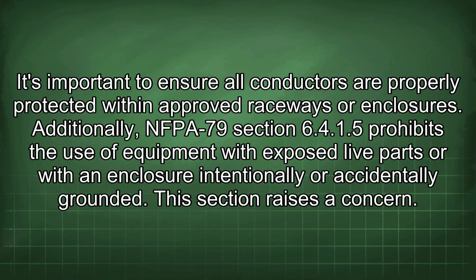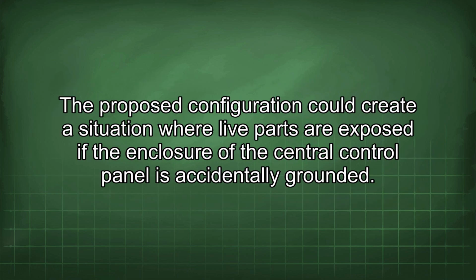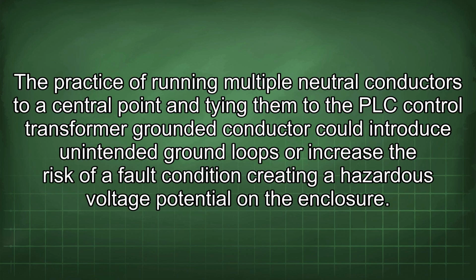Additionally, NFPA 79 Section 6.4.1.5 prohibits the use of equipment with exposed live parts or with an enclosure intentionally or accidentally grounded. This section raises a concern. The proposed configuration could create a situation where live parts are exposed if the enclosure of the central control panel is accidentally grounded. The practice of running multiple neutral conductors to a central point and tying them to the PLC control transformer grounded conductor could introduce unintended ground loops or increase the risk of a fault condition, creating a hazardous voltage potential in the enclosure.